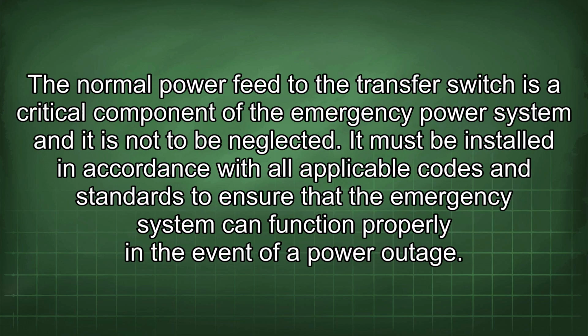The normal power feed to the transfer switch is a critical component of the emergency power system and it is not to be neglected. It must be installed in accordance with all applicable codes and standards to ensure that the emergency system can function properly in the event of a power outage.